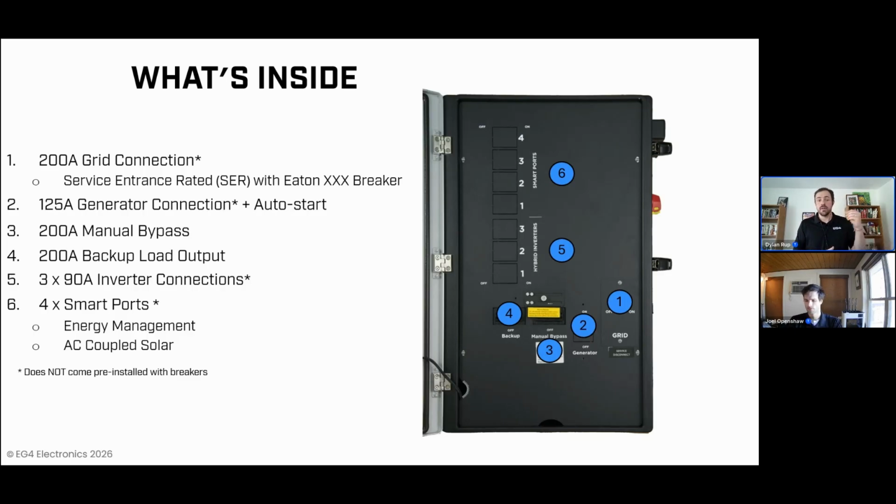Again, significantly reduces what you're going to see with other energy storage systems offering that capability by building that all in. Now, like Joel mentioned before, you do need to consider the overcurrent protection requirements for these different points of connection of either power sources or loads. The GridBOSS is compatible with both BSB breakers, which can be purchased through your distribution partner that carries EG4 equipment. That's a specific breaker type that was designed to pair with the GridBOSS, or we also support Eaton BR breakers, which can generally be purchased off the shelf at any big box retailer or any electrical distributor that your team likes to do business with.